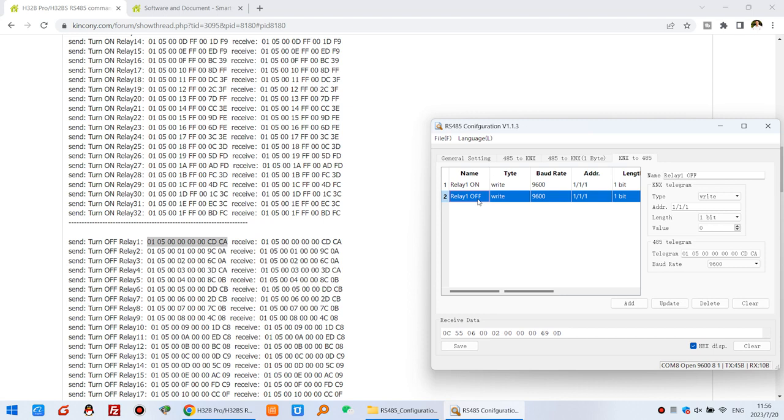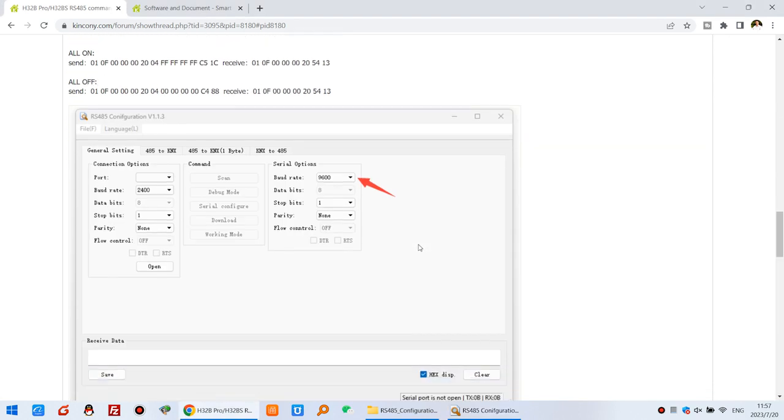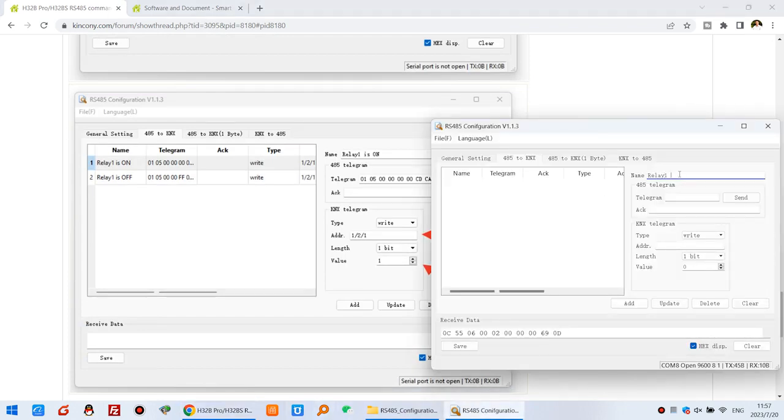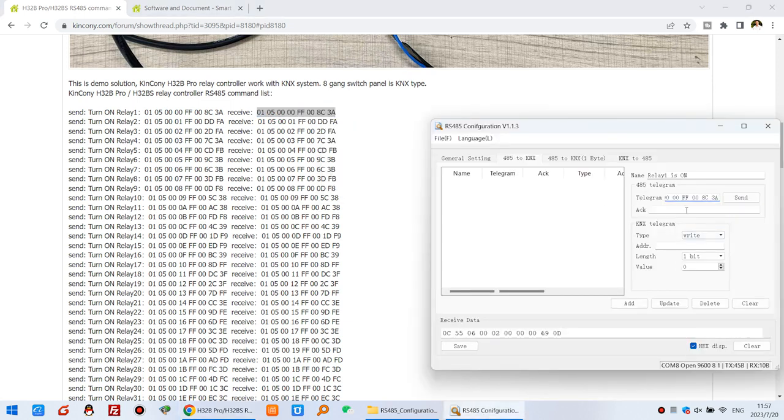But we need to use feedback, so the RS485 needs to feed back to the KNX bus system. So we can also create two states. You can see here — that is for the state. If Relay 1 is on, we will confirm this RS485 Modbus protocol — what protocol. And you can see here: if Relay 1 is on, we will receive this message. So this message will send to the KNX system. So I can copy and paste it here. And also you can click Send — that can test on the KNX bus. If you open your ETS and click Group Monitor, just check the state.